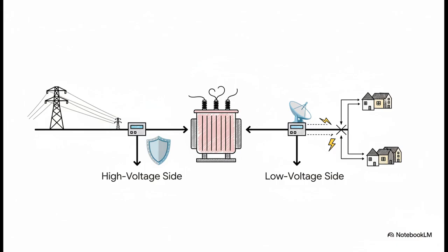But don't let the simplicity fool you. Where you place this guard is actually really strategic. On the high voltage side, it's set up as a backup, smart enough not to trip for every little problem happening miles away. On the low voltage side, its job is to act as a safety net, catching any local faults that other devices might have missed. It's all about making sure the right device handles the problem without causing a bigger blackout.